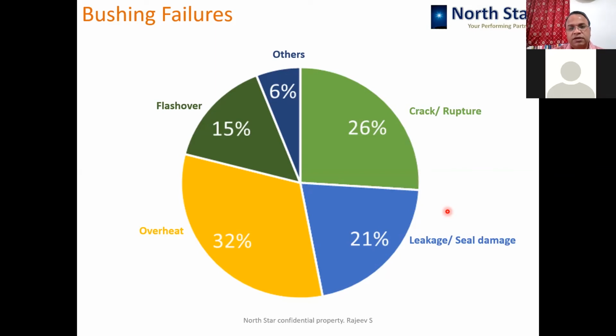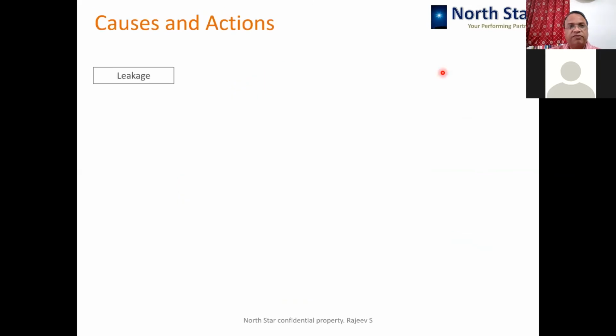Then the second category is crack and rupture. The bushings crack or fail because of pressure development inside, some mechanical damage, or excessive stress. The third reason is leakage and oil seal damage, followed by flashover, and then several reasons contributing to 6%. So this is how the bushings fail.